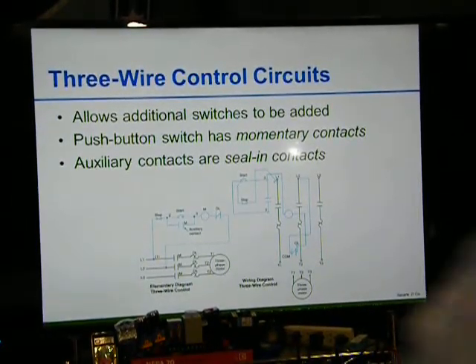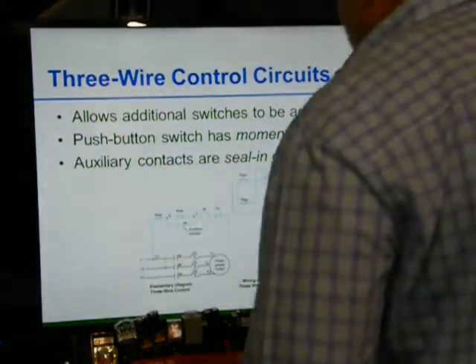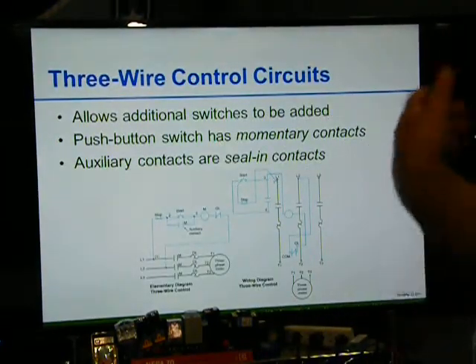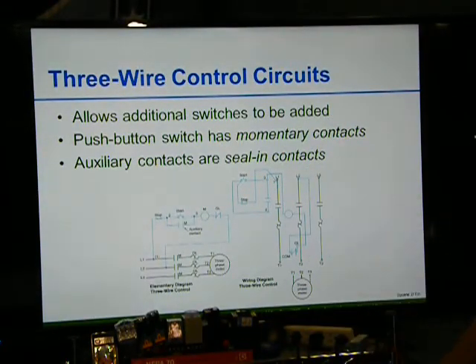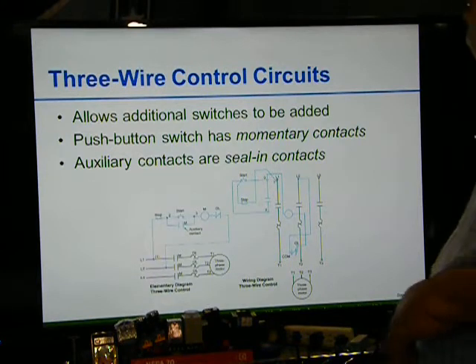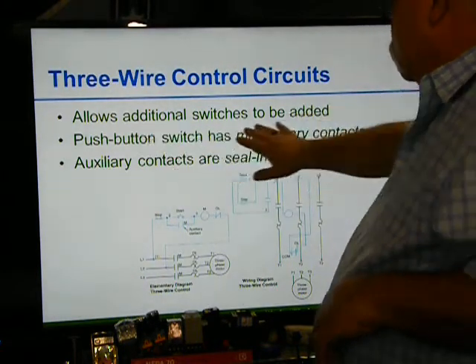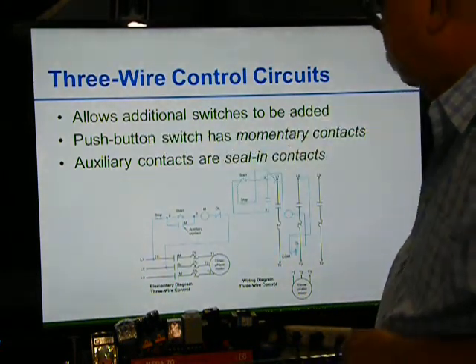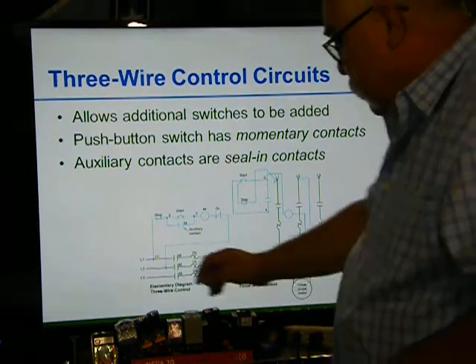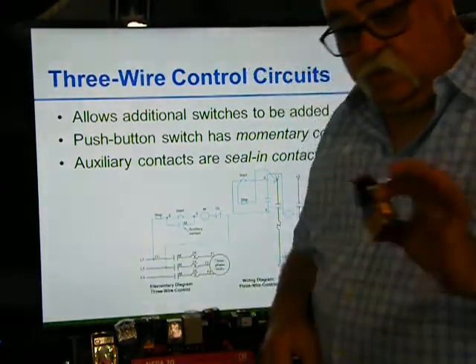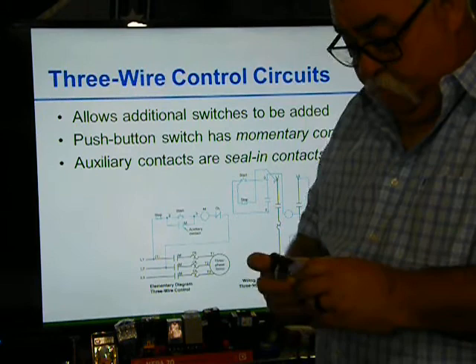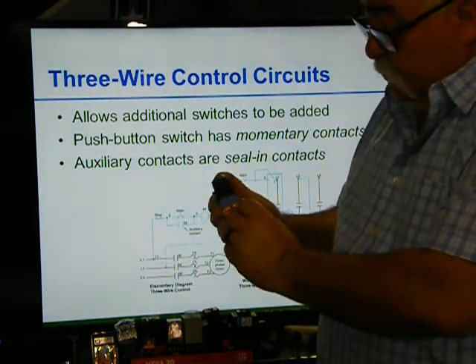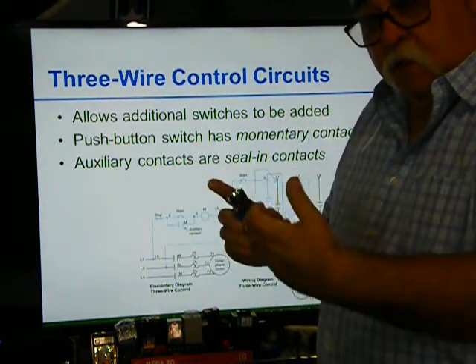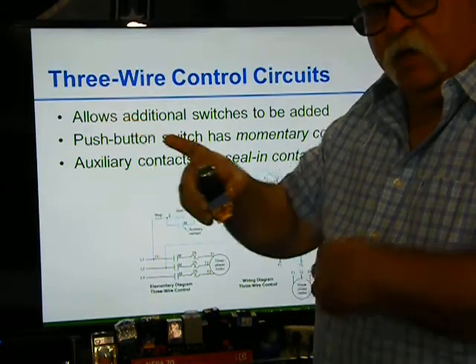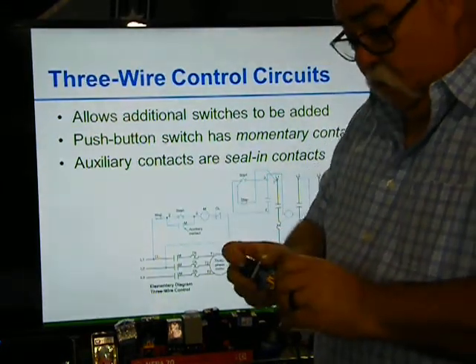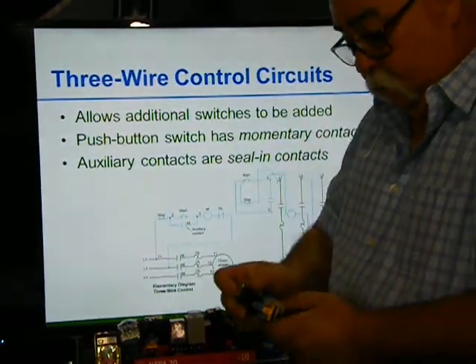Alright, we left off on a 3-wire control circuit. So the advantage of a 3-wire over a 2-wire is that it allows additional switches to be added. When we use these momentary switches, these are called momentary switches. So here on the side it has a spring, makes momentary contact. When we release, it releases. So it only makes that temporary signal.